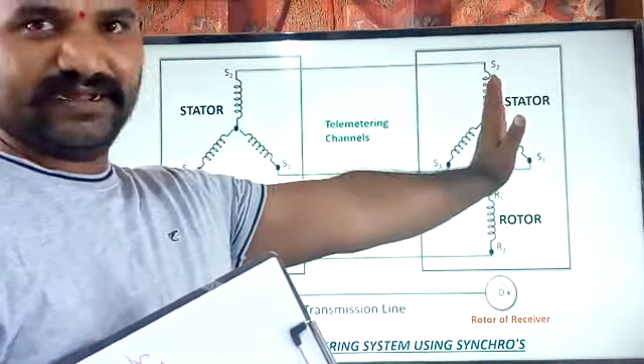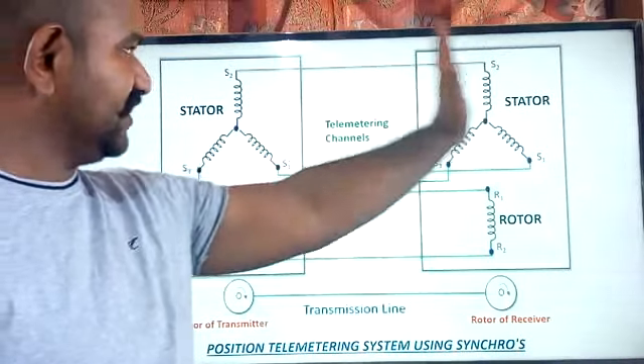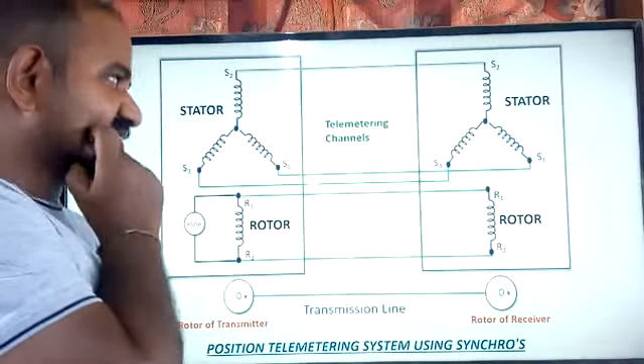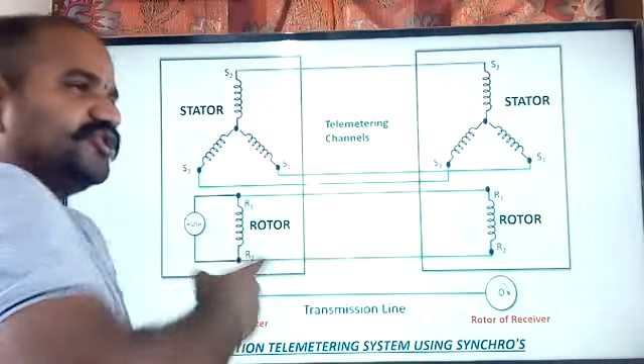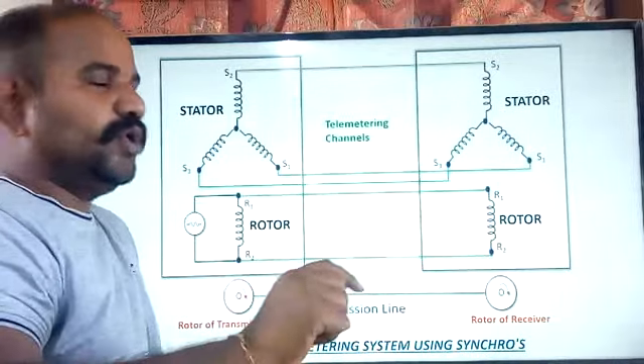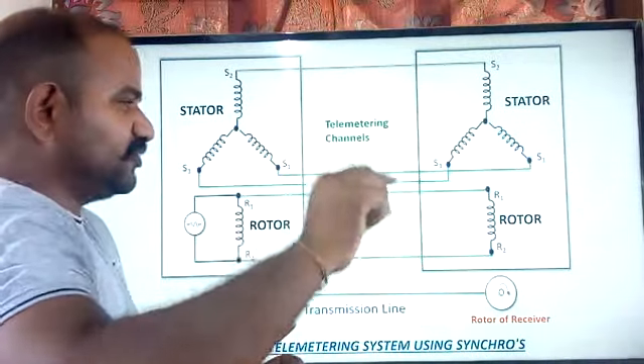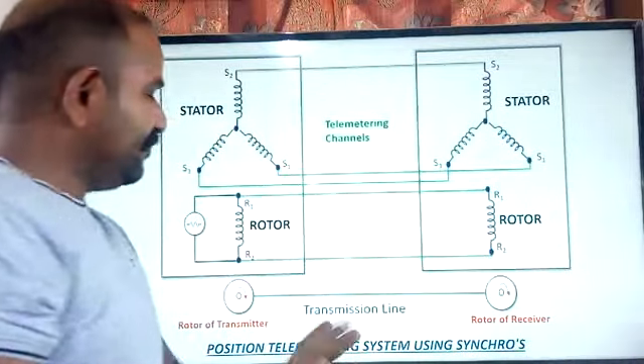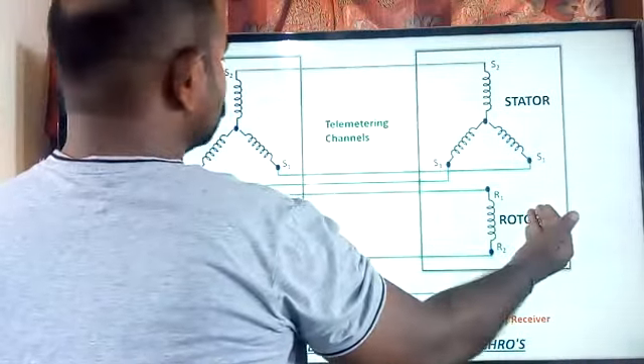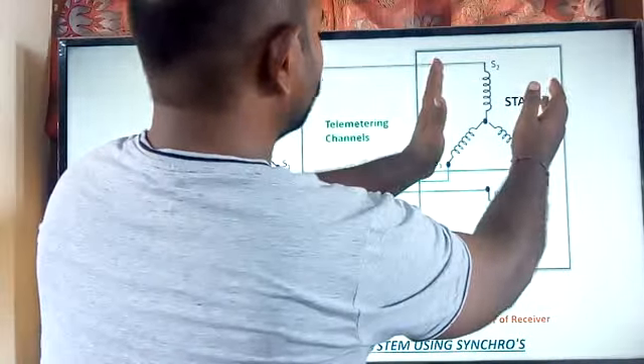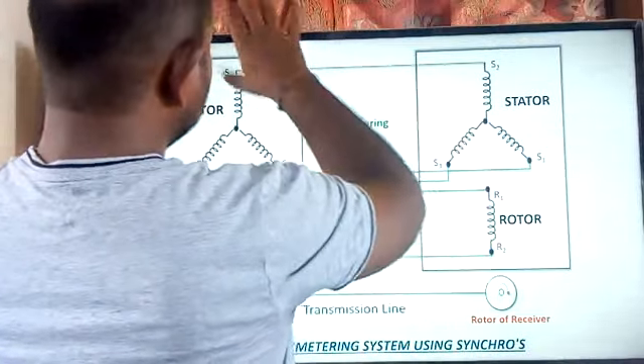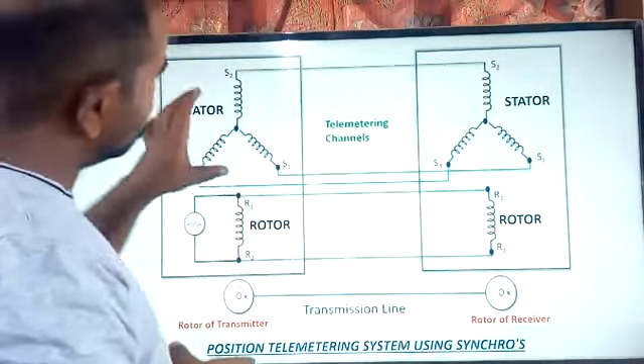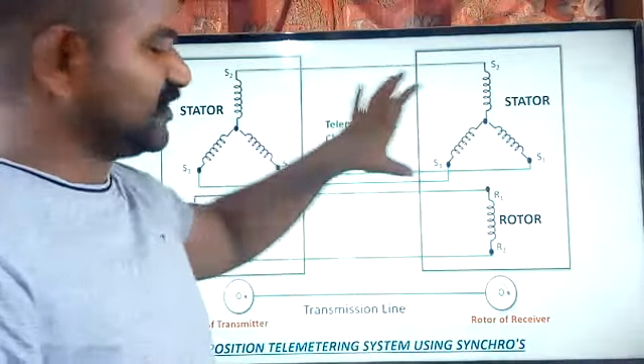This is the transmitting end and this is the receiving end. Before starting the telemetering system, the rotor position is adjusted to a null value. We expect that when this rotor is adjusted to a particular position, the receiver rotor is also at the same angular position. When both are in the same position, the induced EMF at both ends is equal, so the current passing through the channel is zero.